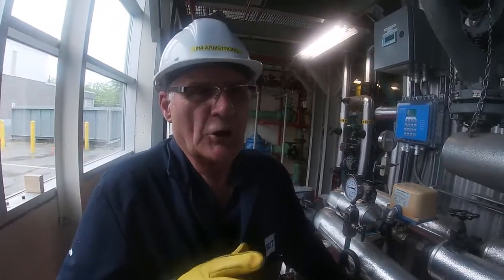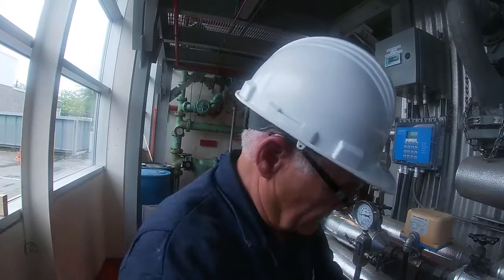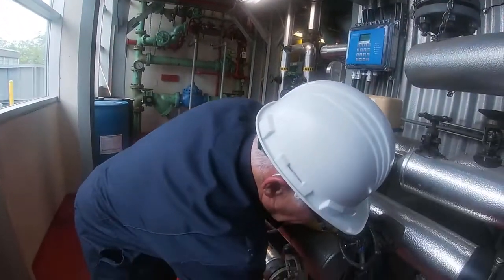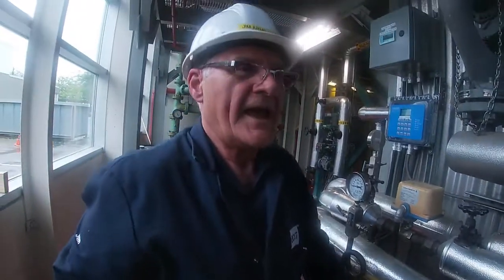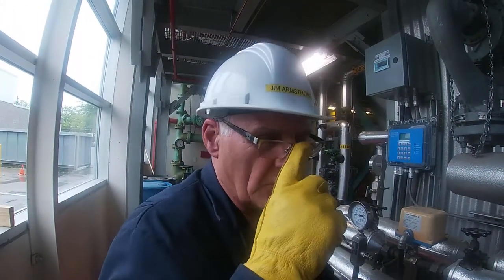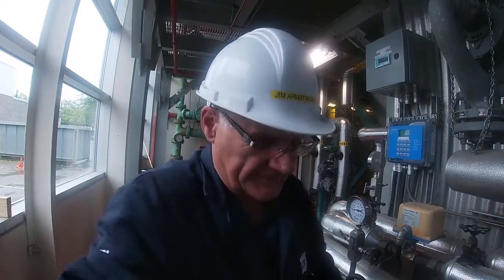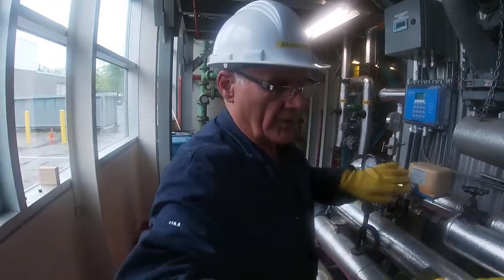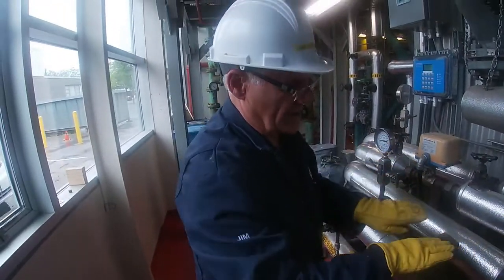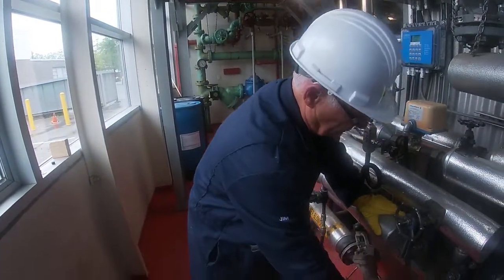So there is another blowdown, a much larger blowdown, and for most boilers, depending on the condition of your feed water coming in, many plants could be blowing down through the bottom blow valve, this guy here. In an earlier clip you would have seen a trough at the bottom of the mud drum where the liquid would come into it and then come out through this blowdown valve.